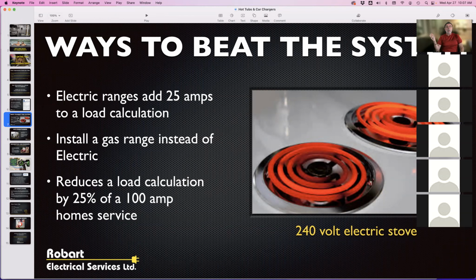So think about this: if you've got a 100 amp service and your stove by itself takes 25 amps, that all adds into the end result. One way of overcoming this and reducing your demand is to install a gas range—you've now removed 25 amps from the load calculation. These are cases, ladies and gentlemen, where you've exceeded your service and you've got to start looking at ways of reducing it to be able to get your permits and so forth from the city.